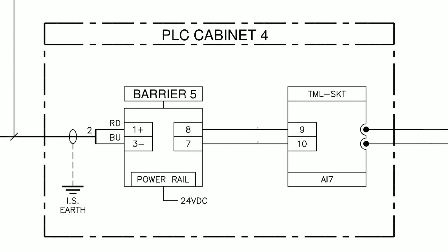Within the PLC Cabinet we can see the connections go into Barrier 5. Now the barrier is a device that is used to allow equipment to be powered in hazardous area or areas where explosive atmospheres are present. The barrier allows the equipment to be powered without creating a spark that would have enough energy to ignite an explosive atmosphere thus providing the protection from explosion. We'll talk more about barriers and hazardous area equipment in future videos. We can also see this barrier is externally powered via a 24 volt DC power rail. Some barriers are powered by the PLC directly but this one has a separate 24 volt DC supply.